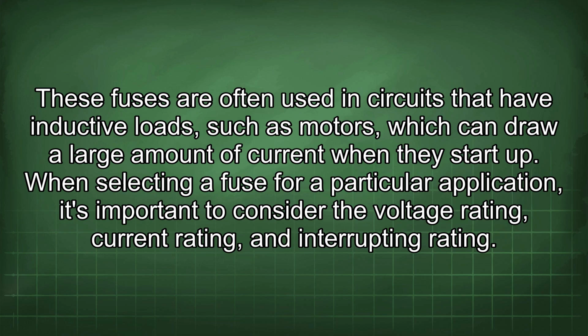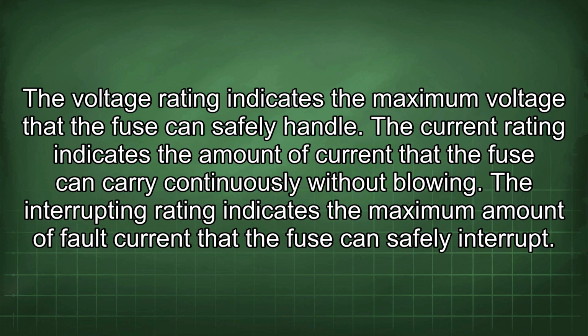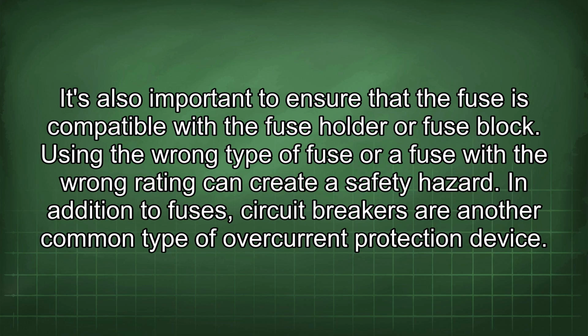When selecting a fuse for a particular application, it's important to consider the voltage rating, current rating, and interrupting rating. The voltage rating indicates the maximum voltage that the fuse can safely handle. The current rating indicates the amount of current that the fuse can carry continuously without blowing. The interrupting rating indicates the maximum amount of fault current that the fuse can safely interrupt. It's also important to ensure that the fuse is compatible with the fuse holder or fuse block. Using the wrong type of fuse or a fuse with the wrong rating can create a safety hazard.